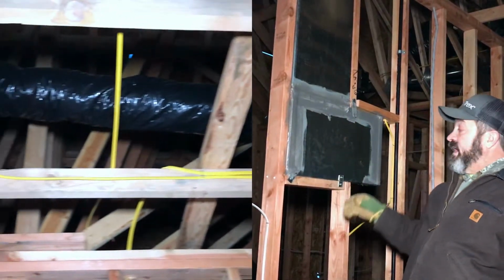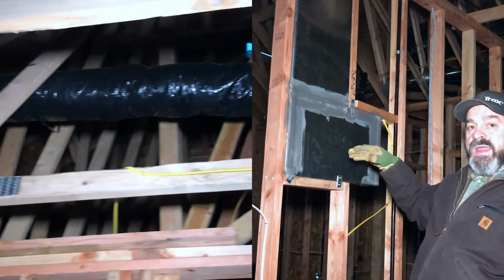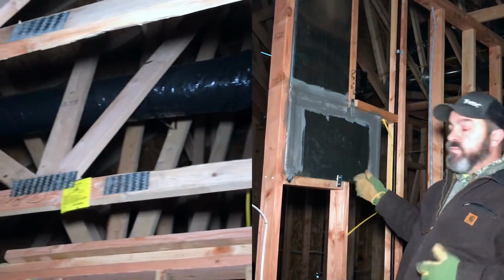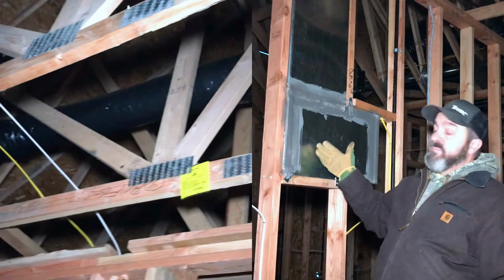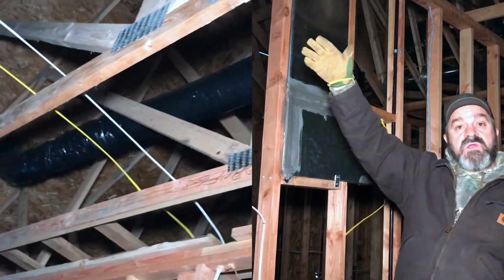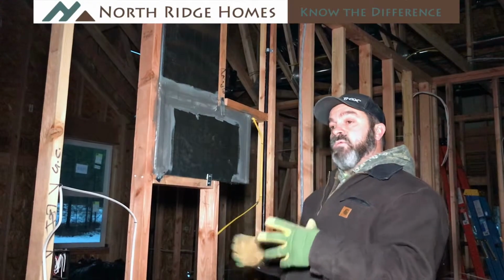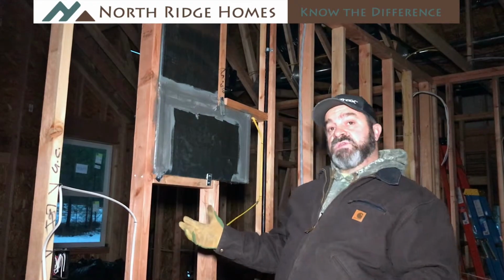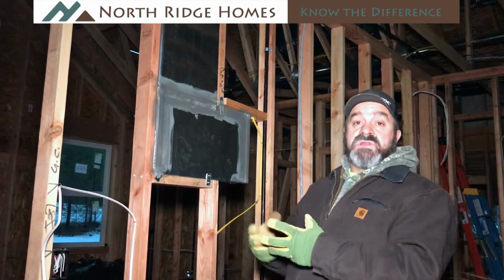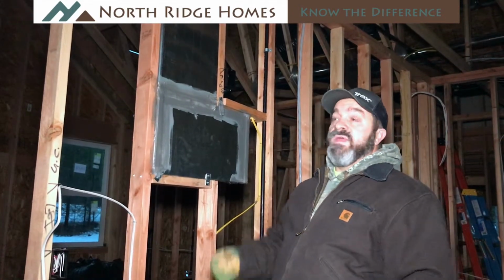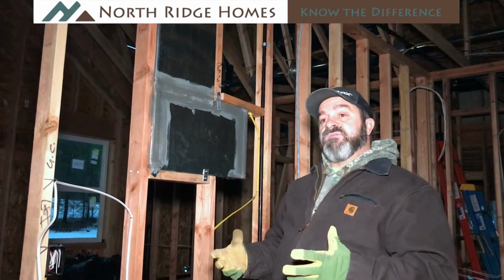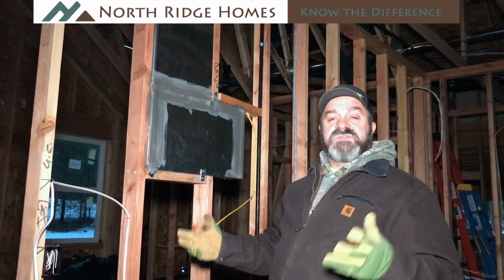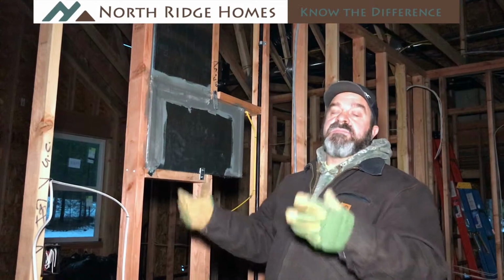The reason for that is you're going to have hot, warm air, sometimes with steam from cooking, that comes up through your hood and goes out through the attic. When it passes through the attic in winter, the attic is cold and the pipe warms up, so it wants to condensate and sweat. That insulation prevents that from happening so you don't have sweat dripping off your pipes and damaging your drywall.